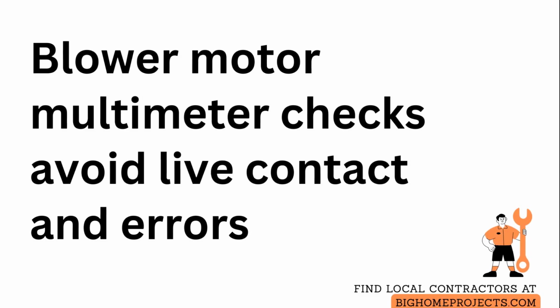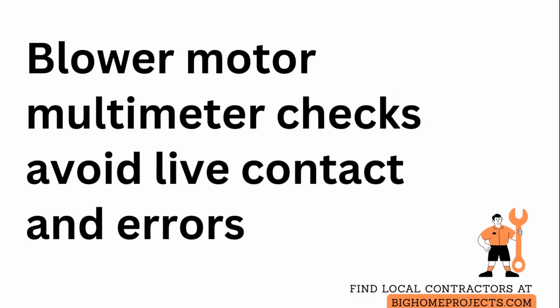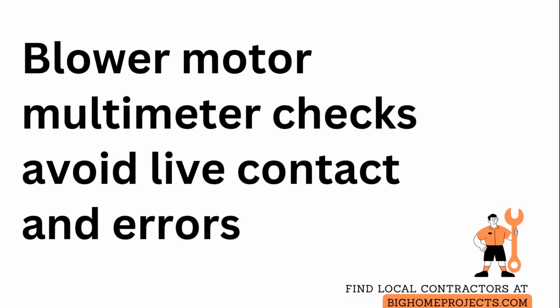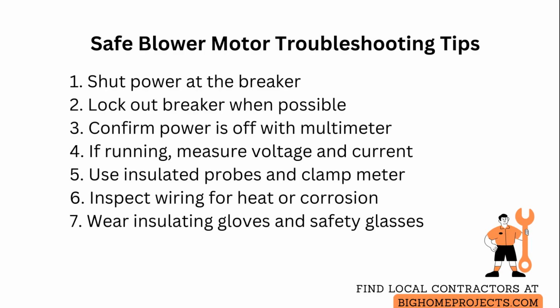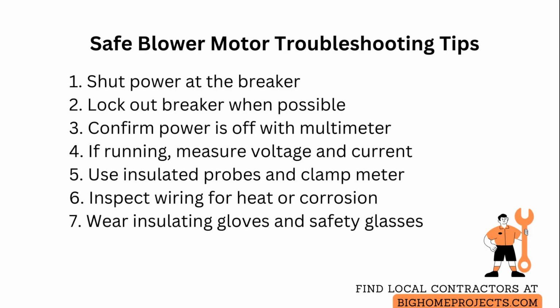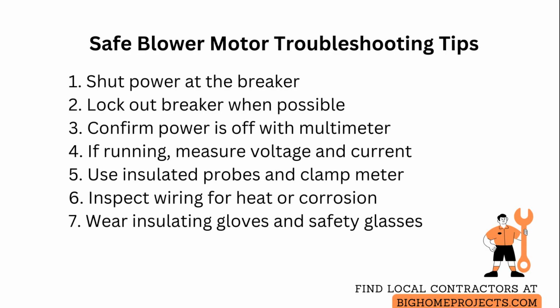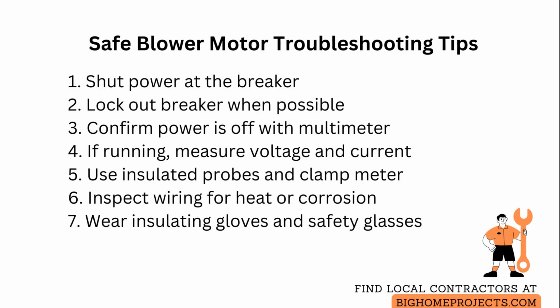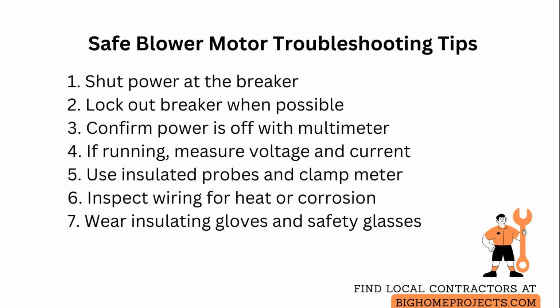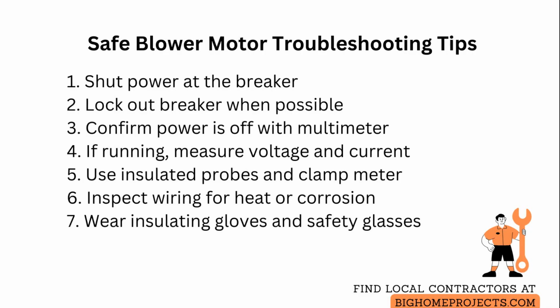No, it is not safe to troubleshoot a running blower motor without a multimeter. A blower motor circuit can carry lethal voltages and present wiring faults that are invisible to the naked eye, so always verify live circuits with a properly rated multimeter before touching anything. Start by shutting power at the circuit breaker and lock it out where possible. Then confirm power is off at the motor terminals with the multimeter set to the appropriate voltage range.